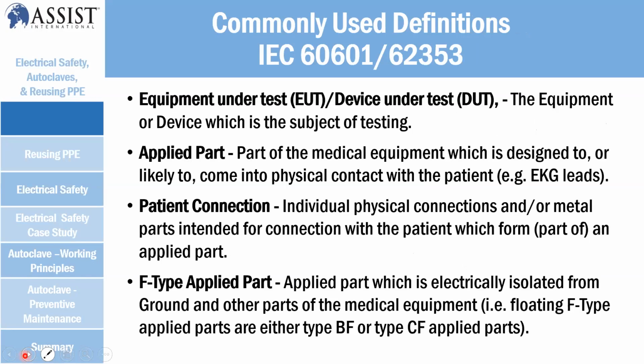In IEC 60601, there are a lot of symbols and details that you need to know when you do a safety test. For example, the terms they use: equipment under test, EUT, DUT, and so on. EUT means equipment under test, and DUT is device under test. And applied parts. An applied part is like the ECG, SpO2, patient connection, type of connection. Then F-type applied parts are isolated between the ground and the equipment.